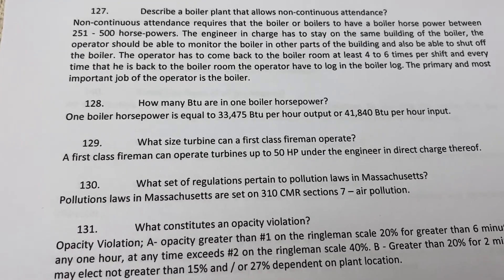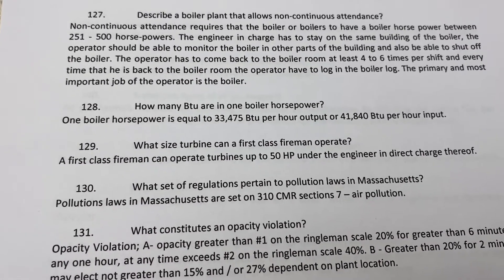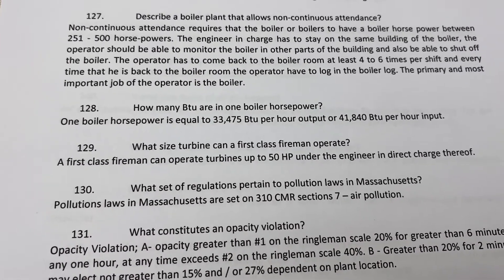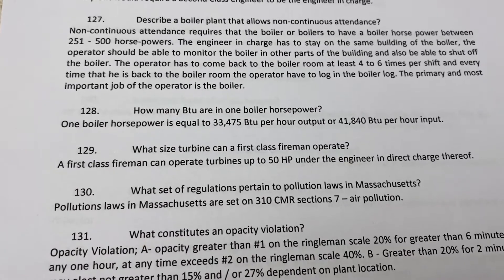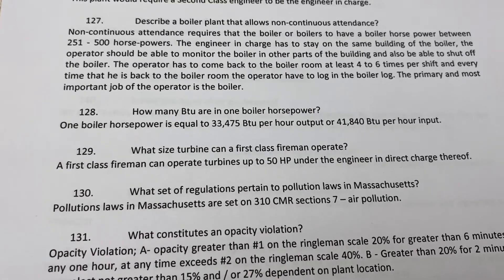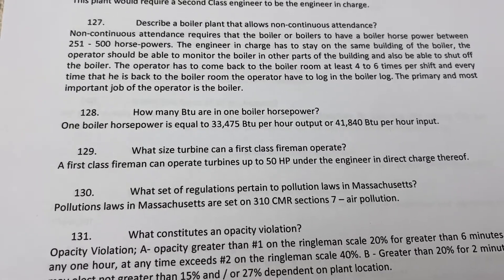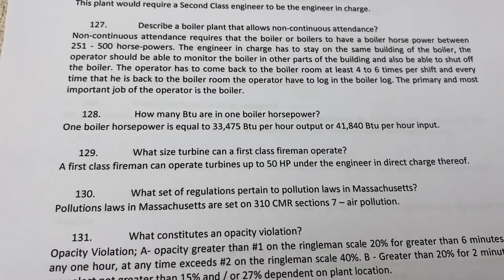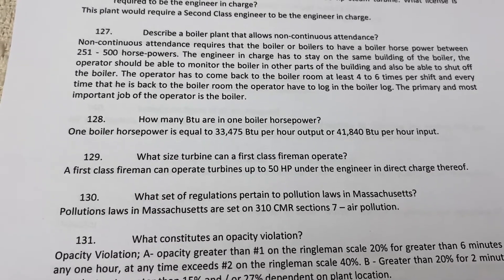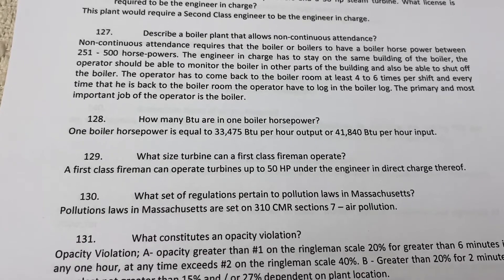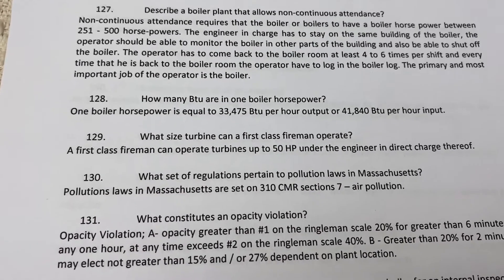How many BTUs are in one boiler horsepower? One boiler horsepower is equal to 33,475 BTU per hour output, or 41,840 BTUs per hour input.